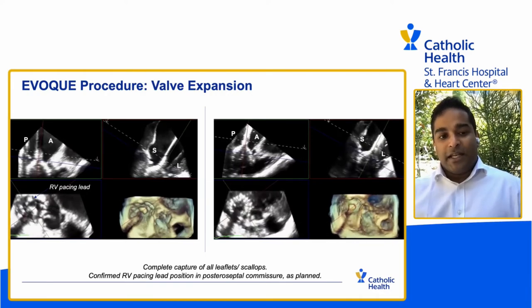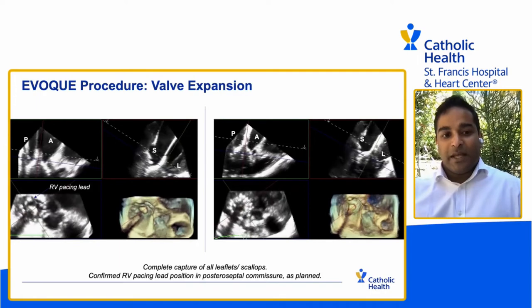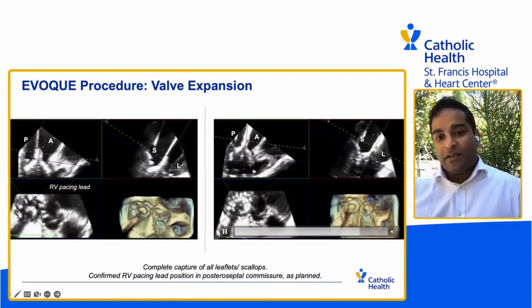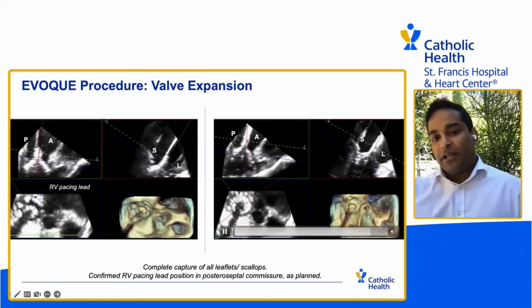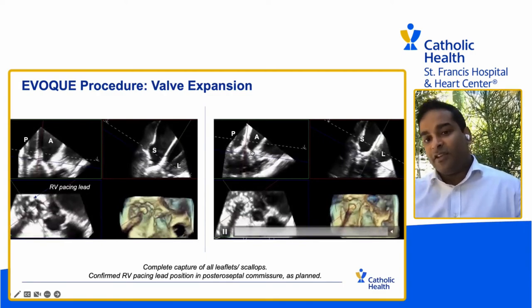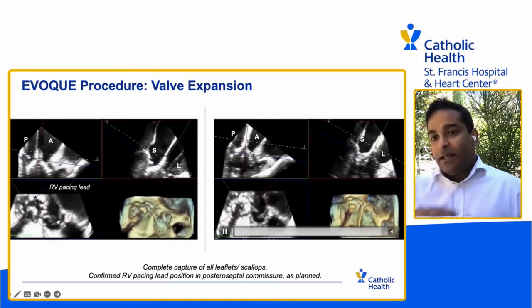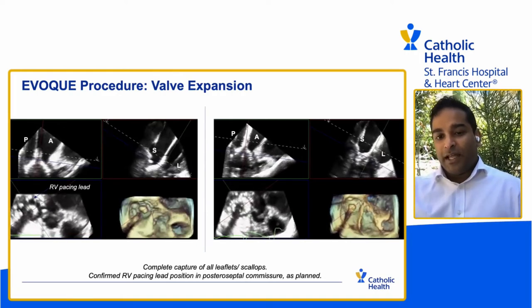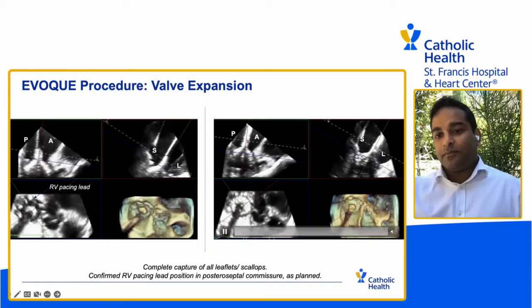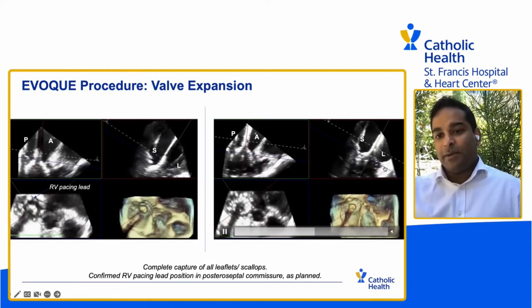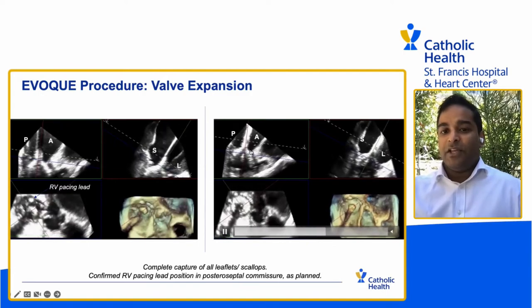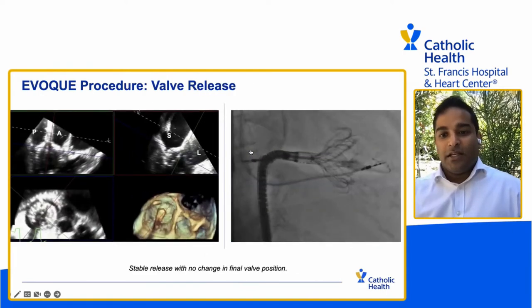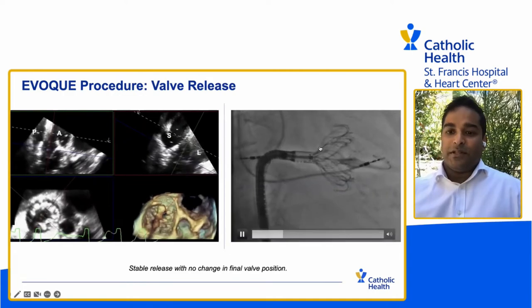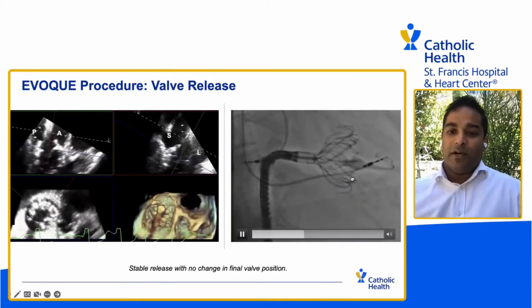When all nine of those anchors are on the outside of the leaflets and the leaflets are coming in nicely to the body of the valve, we expand the ventricular portion and then slowly reduce the depth of the implant, either by pushing on the RV wire or by retracting the capsule with the controls on the handle, to bring the anchors close to the annular plane. Once the anchors are close to the annular plane and we feel that the valve is coaxial to the tricuspid annulus, we can release this valve.